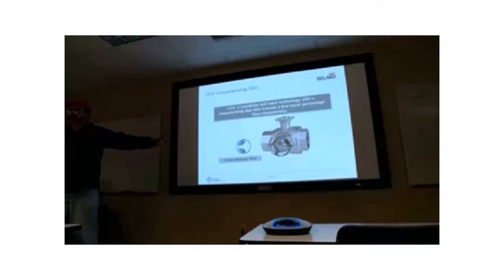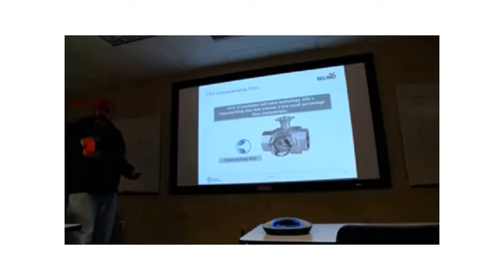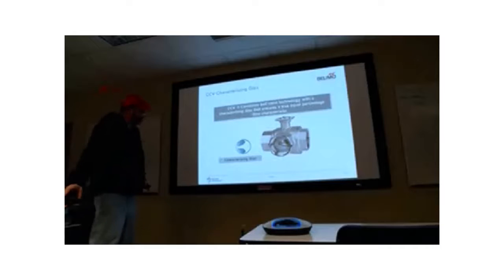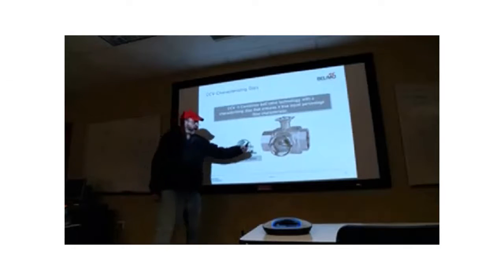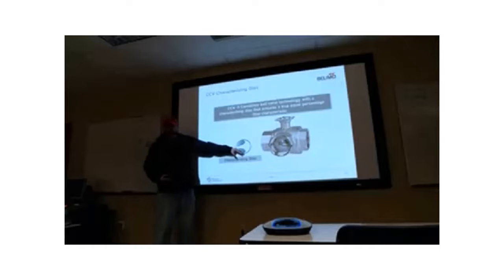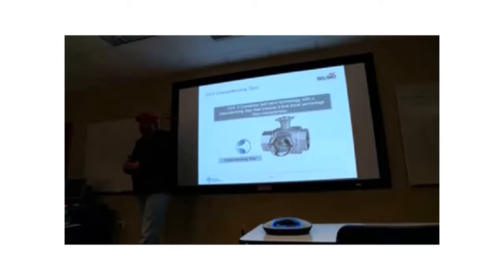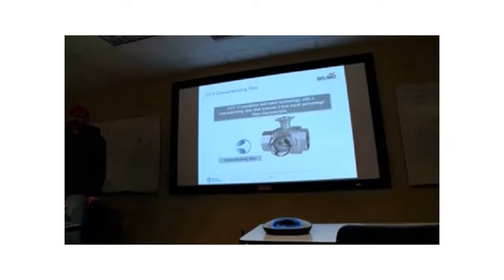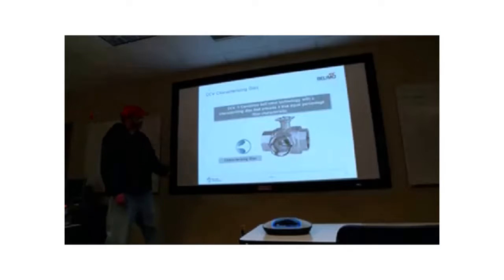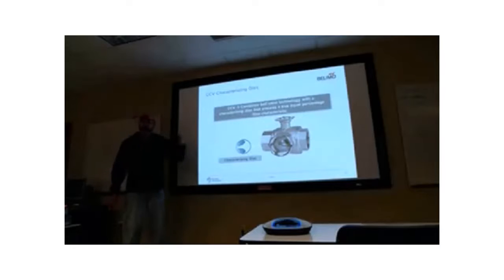So when we came into the market, we came in with this characterized control valve. We said, okay, we'll take a ball valve, we'll make this characterizing disc, we can characterize the flow to make it an equal percentage valve, and we can do it for half the cost. We did that in 1998, and now everybody has one, right? Because imitation is the best form of flattery. Siemens has one, Johnson has one. But we were the original people that came up with this idea of using a ball valve to control a terminal coil. And we do it with this disc.